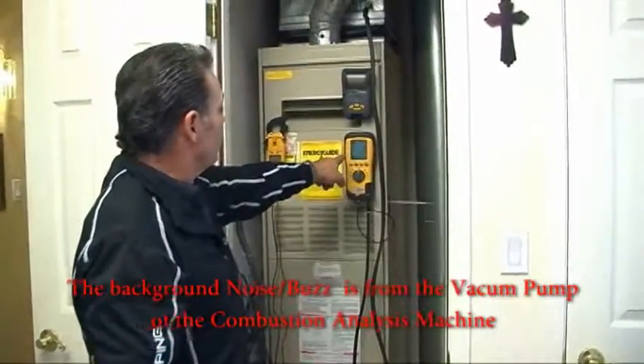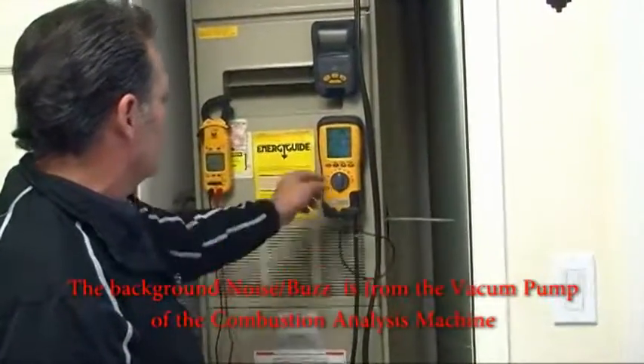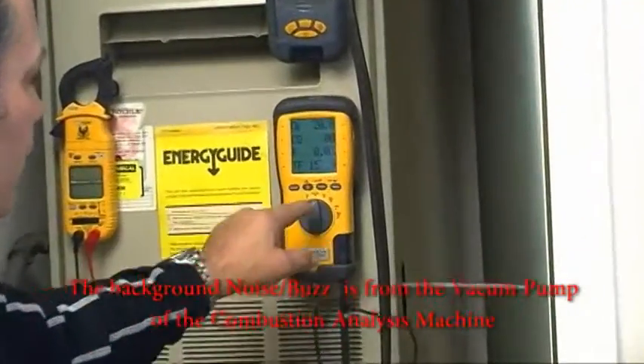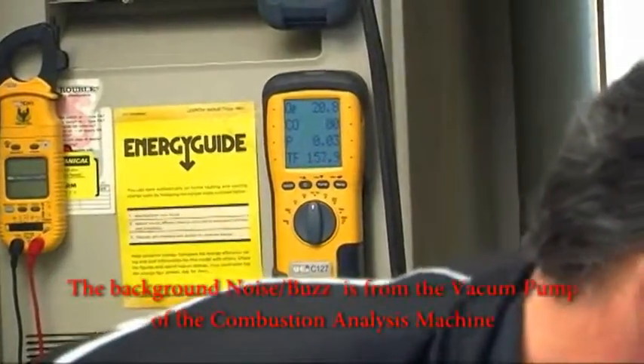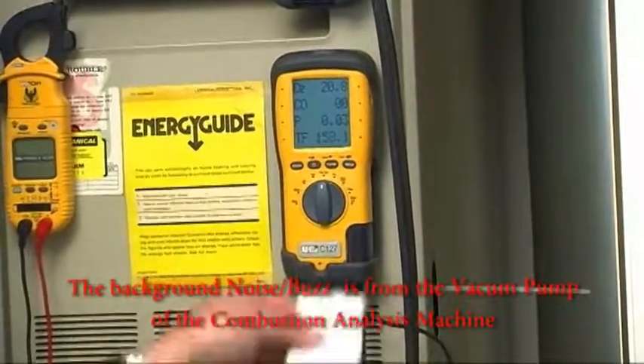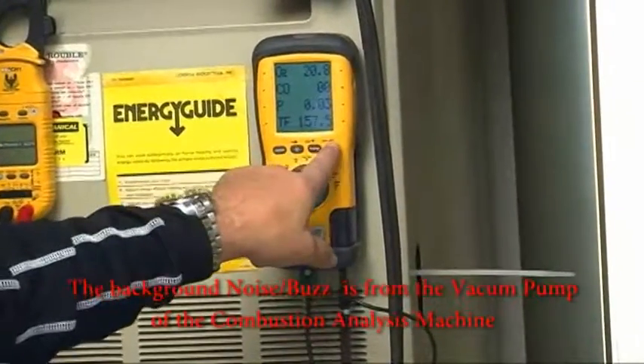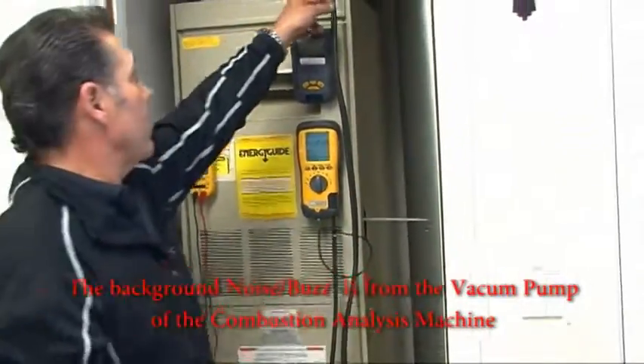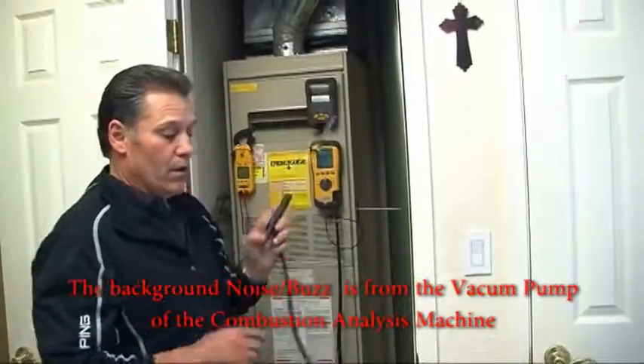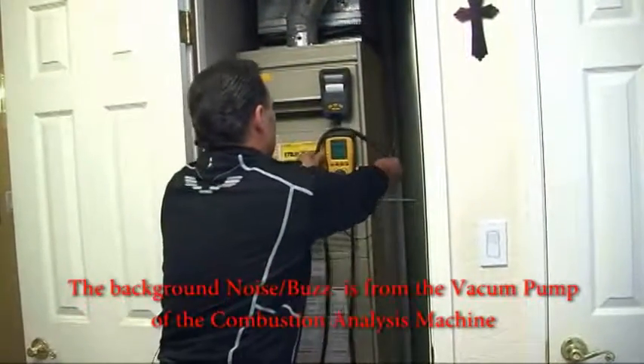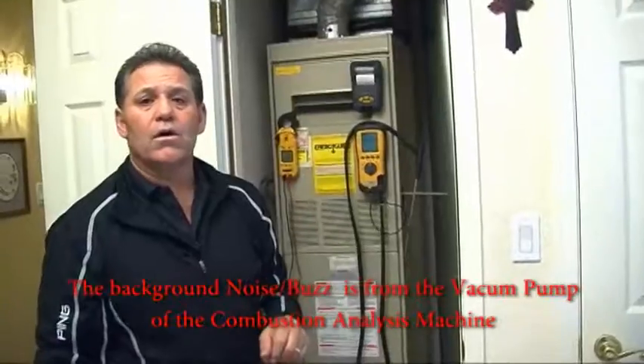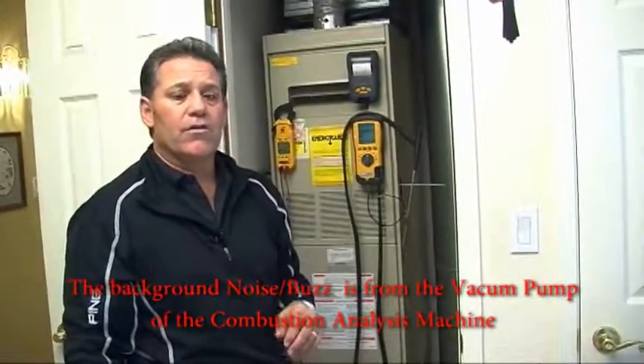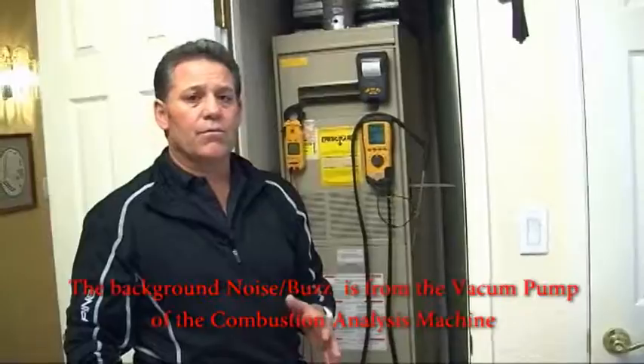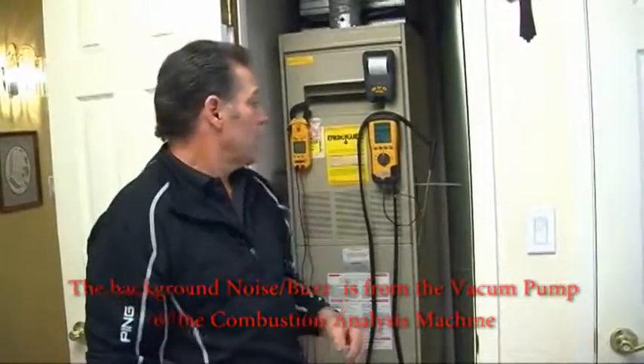We can see here that carbon monoxide we have absolutely zero. This is the supply air test. Our temperature in the supply is similar to the temperature of the supply air we had earlier. So we're going to go ahead and print this one also, and that is going to show that we don't have any carbon monoxide at all inside of the supply plenum. That is how you should do a combustion analysis to be sure that you're giving your customers the most proper and effective testing. Thank you for watching.